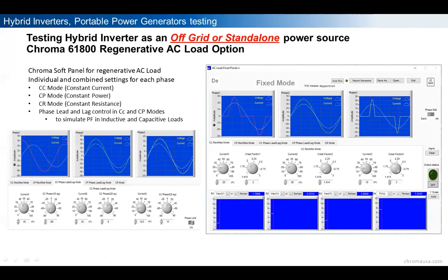So our off-grid test for that would still be our 61800 regenerative grid simulator, but we can use it in AC load function. And what we do is we can create a load that will simulate peaks, various peak types of currents, as you can see in the waveforms here, various types of peak currents. We can also do true phase shift between voltage and current to create power factors.